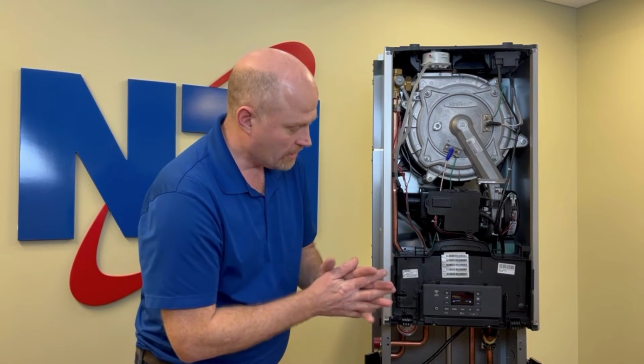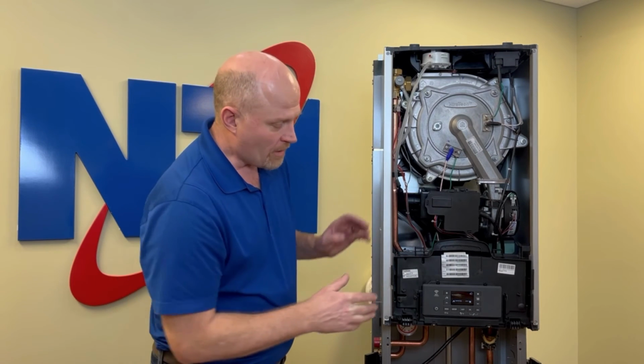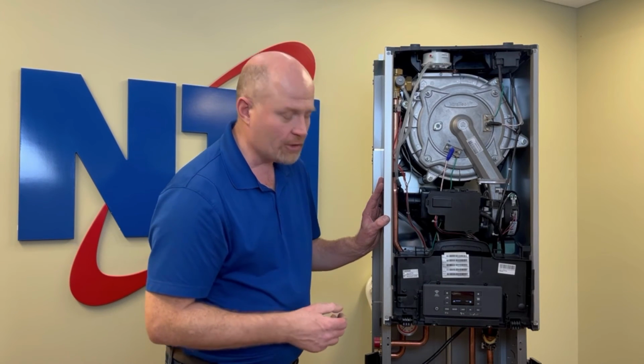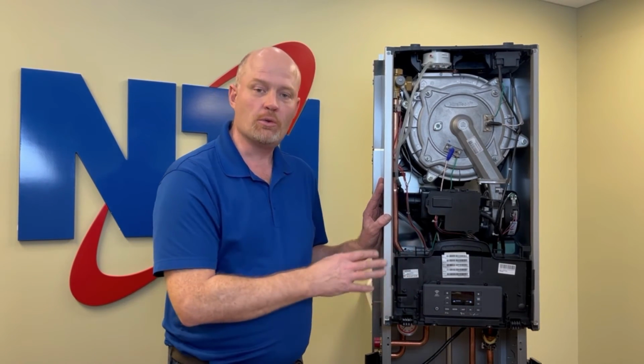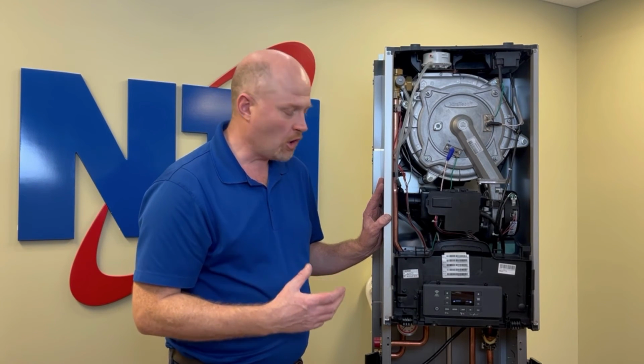The sensor that connects here is a 10 kilo ohm thermistor. These are a standard component through the industry. If you look in the back of the installation manual, there's a temperature resistance chart that will give you the readings you should expect to see. However, if you go and Google 10K NTC or 10K thermistor and look at the resistance reading chart, just about any of them are going to be close enough that you can decide whether your sensor is working or not.